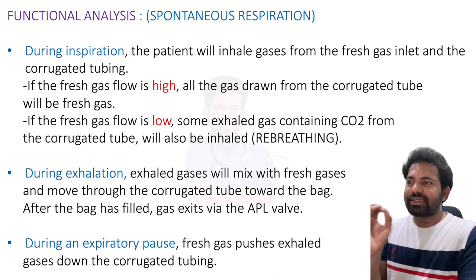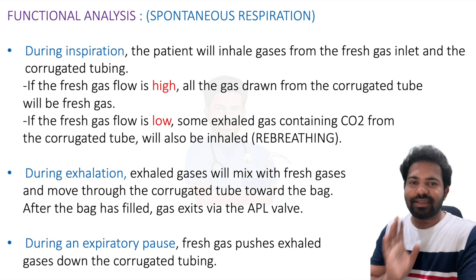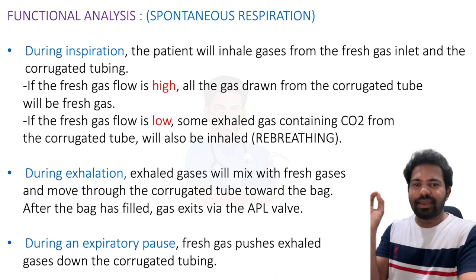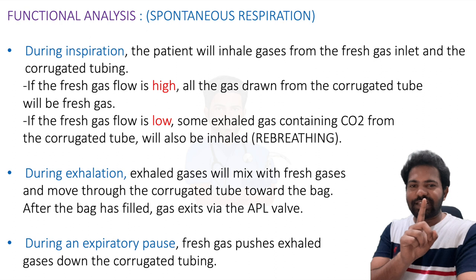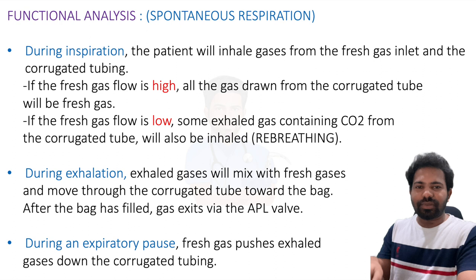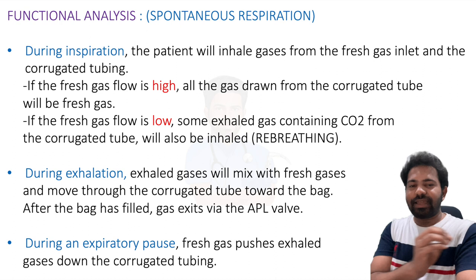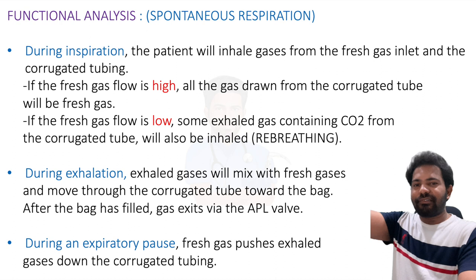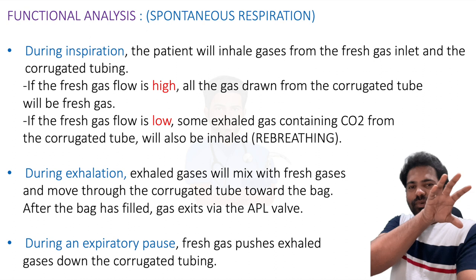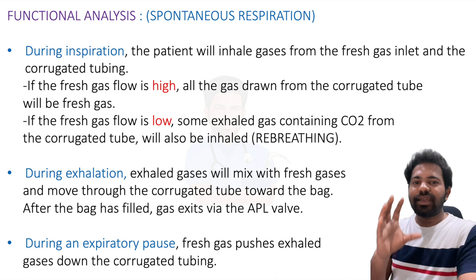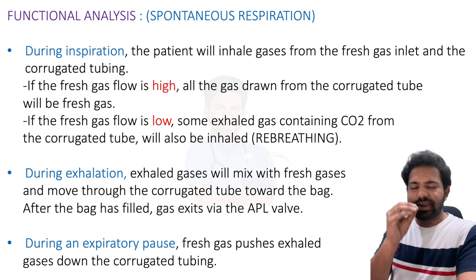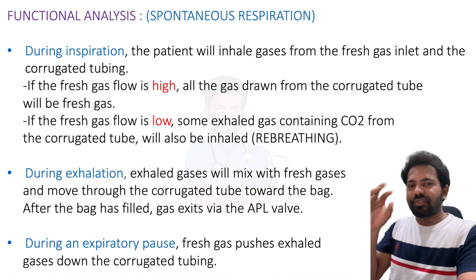If the fresh gas flow is high, all gases drawn from the corrugated tube will be fresh gas. When the patient expires, expired gases travel through the corrugated tube — some go into the reservoir bag and most are expelled through the APL valve. When fresh gas flow is very high it pushes all expired gases through the APL valve to the atmosphere. But if fresh gas flow is low, fewer expired gases are expelled and some remain in the corrugated tube, leading to re-breathing.